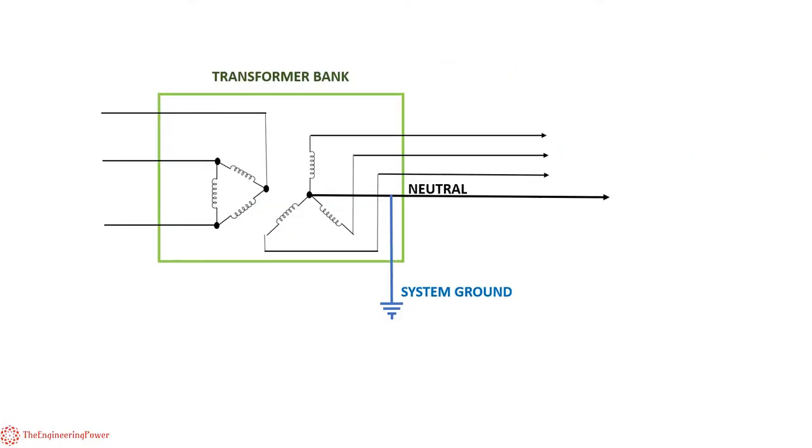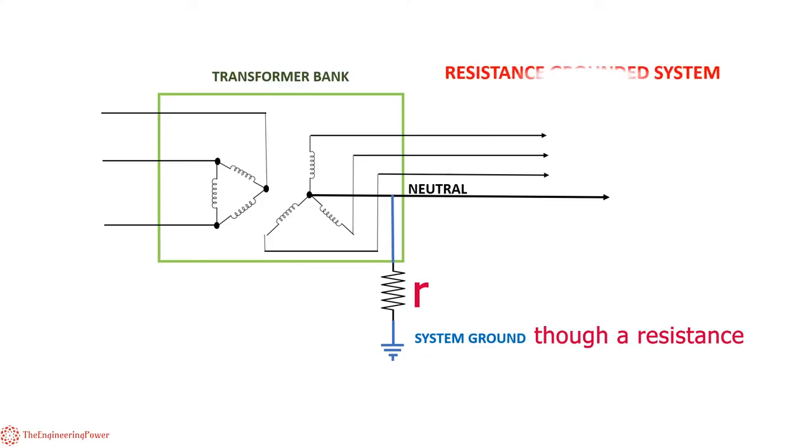In grounding, system neutral may be connected to earth with or without any resistance or impedance. If the neutral is connected to earth without any resistance, it is known as a solidly grounded system. In case the system neutral is connected to earth through a resistance, such system is called a resistance grounded system.